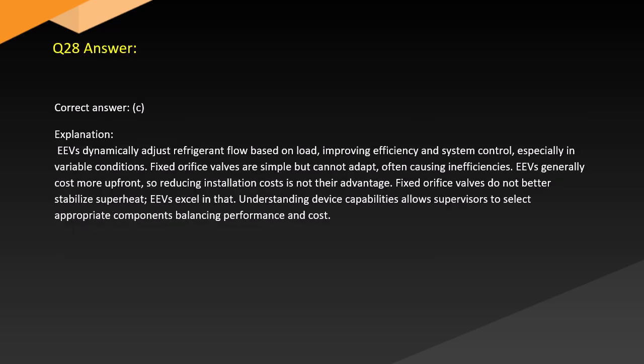Answer. Correct answer, C. Explanation. EEVs dynamically adjust refrigerant flow based on load, improving efficiency and system control, especially in variable conditions. Fixed orifice valves are simple but cannot adapt, often causing inefficiencies. EEVs generally cost more upfront, so reducing installation costs is not their advantage. Fixed orifice valves do not better stabilize superheat. EEVs excel in that. Understanding device capabilities allows supervisors to select appropriate components, balancing performance and cost.